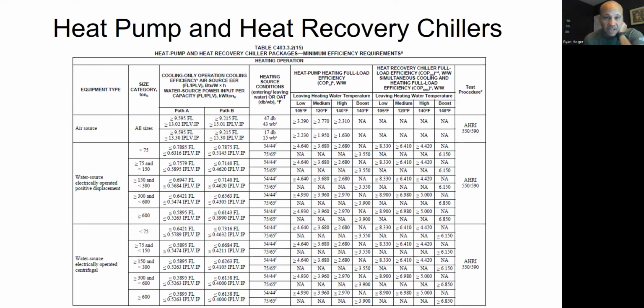When you look at these tables, and this is similar to other things in the code, I know it's a little bit small for you guys, but I'll explain it. When you look at the efficiency of stuff you have to do for the International Energy Conservation Code, which is what you in your state and I in my state follow, you go find the section that you're in first, right? Because there's like 18 pages of equipment efficiencies that you have to hit, plus a bunch of other stuff you have to do other than just equipment. But the equipment has all these different tables. So in our case, we scroll past the heat pump section. We scroll past the chiller section in the document, and we go to the very last section, which is 403.3.2.15, and it says heat pump and heat recovery chiller packages. That's where you got to get over to.